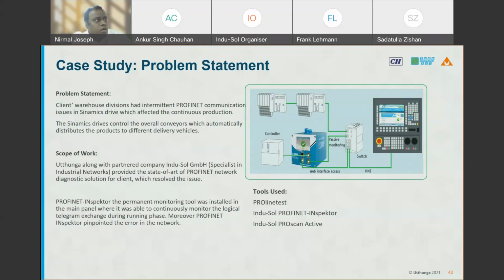Utthunga, along with Indu-Sol, inspected this site and provided network and diagnostic solutions using some tools readily available from Indu-Sol. One of the main tools used during this study was the PROFINET-INspektor, a permanent monitoring tool installed on the main panels beside the PLCs - a brief network connection is shown in the picture. This monitors the controller communication on the PROFINET-INspektor.